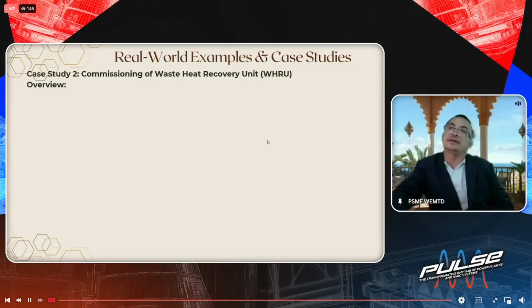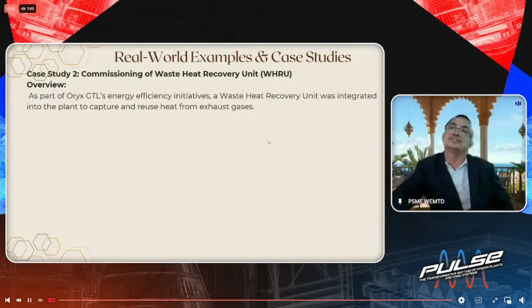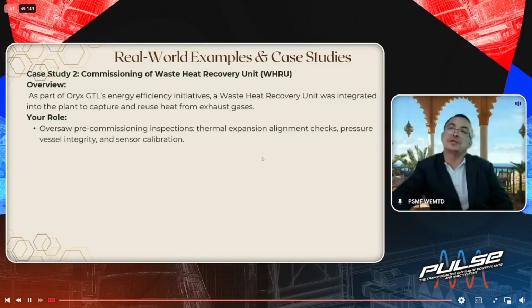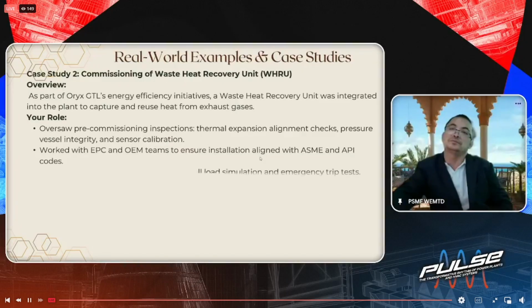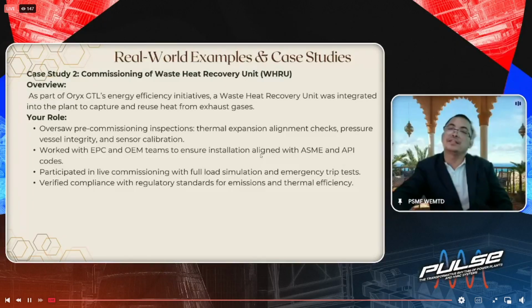What is the WHRU, the waste heat recovery unit? As part of Oryx GTL's energy efficiency initiative, a waste heat recovery unit was integrated into the plant to capture and reuse heat from exhaust gases. This involved overseeing pre-commissioning inspection, thermal expansion alignment checks, pressure vessel integrity, and sensor calibration. We worked with EPC and OEM teams to ensure installation aligned with ASME and API codes, participated in live commissioning with full load simulation and emergency trip tests, and verified compliance with regulatory standards for emissions and thermal efficiency.